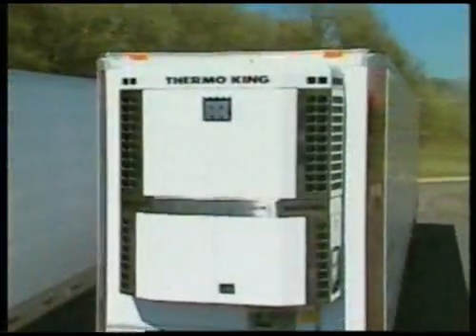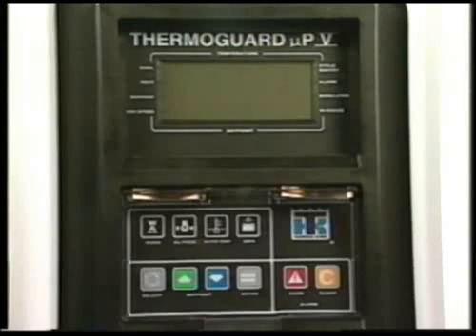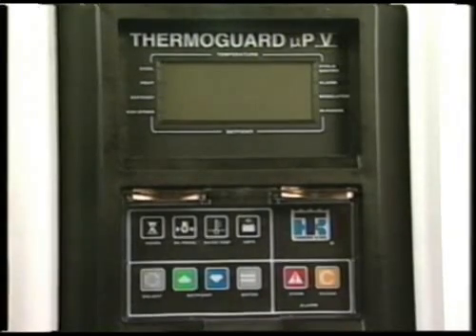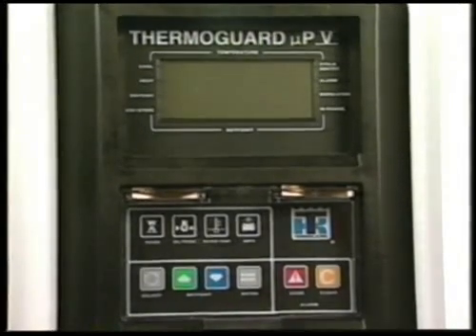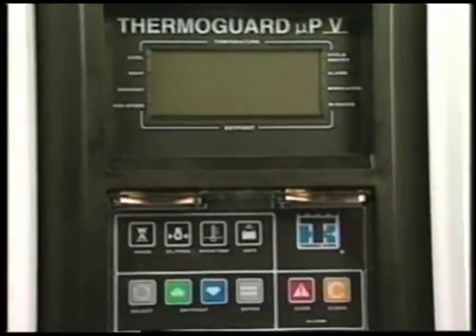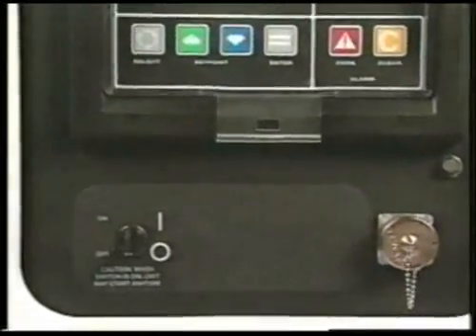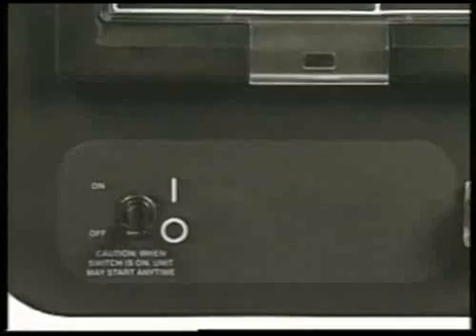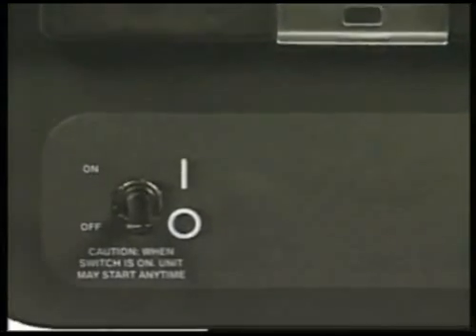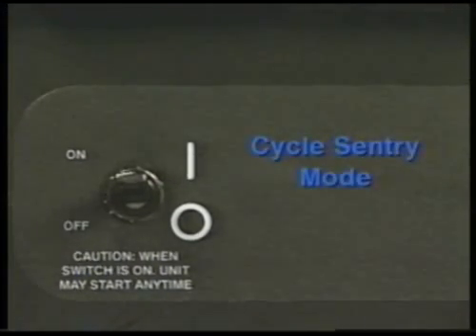We'll use an SB330 WhisperSmart reefer for our demonstration. The controls on King of the Road units are identical in appearance and operation. The front of the ThermoGuard µP-V microprocessor consists of the display and keypad. A switch panel with an on-off switch is located below the microprocessor. The unit will start automatically in about 10 seconds when the on-off switch is turned on and continuous mode is selected, or if cycle sentry mode is selected and conditions require the engine to run.